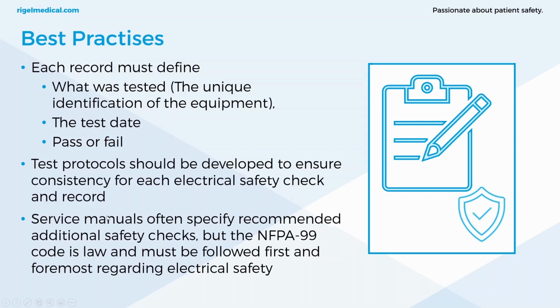It's also worth looking at the OEMs, so the original equipment manufacturer service manuals for their guidance. That's what it states here at the bottom. Service manuals may specify specific checks, but just remember that the NFPA 99 code is law and it must be followed first and foremost when it comes to electrical safety. So to be more thorough, it's always worth contacting the manufacturer to see what they recommend in terms of testing.